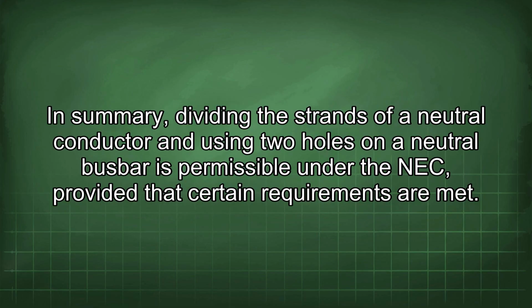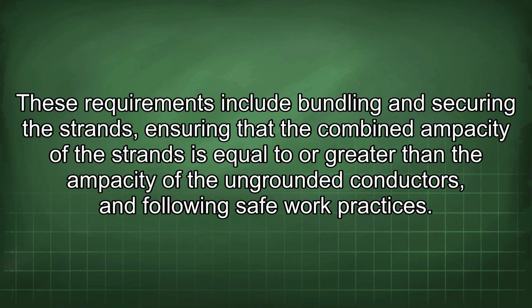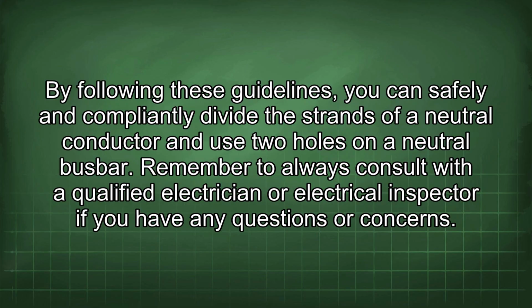In summary, dividing the strands of a neutral conductor and using two holes on a neutral busbar is permissible under the NEC, provided that certain requirements are met. These requirements include bundling and securing the strands, ensuring that the combined ampacity of the strands is equal to or greater than the ampacity of the ungrounded conductors, and following safe work practices. By following these guidelines, you can safely and compliantly divide the strands of a neutral conductor and use two holes on a neutral busbar.